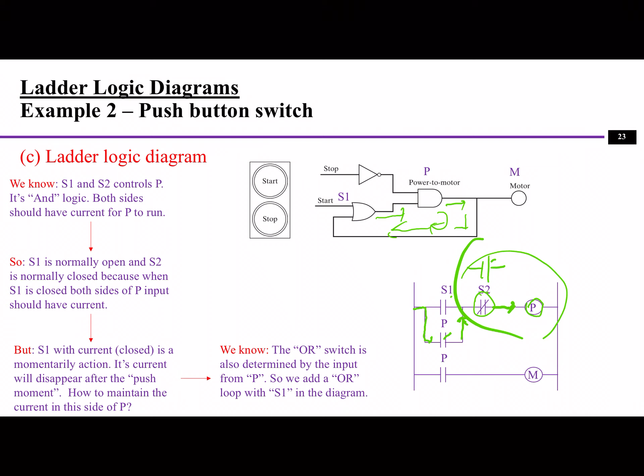So what happens when we push the stop button? We know S2 will change to open. So current will not go through this path, which means that P will go back to open, and this will go back to open again, and M will be shut down, and the motor will not be running. So basically this is the story of what happens when you push the button, release the button, and then stop it. The ladder logic control diagram tells this story.